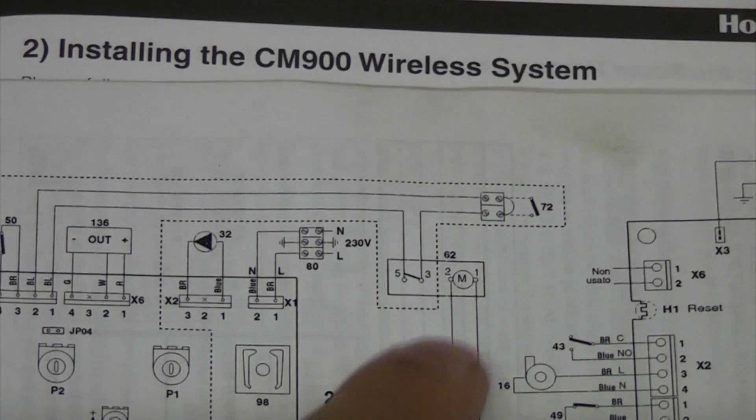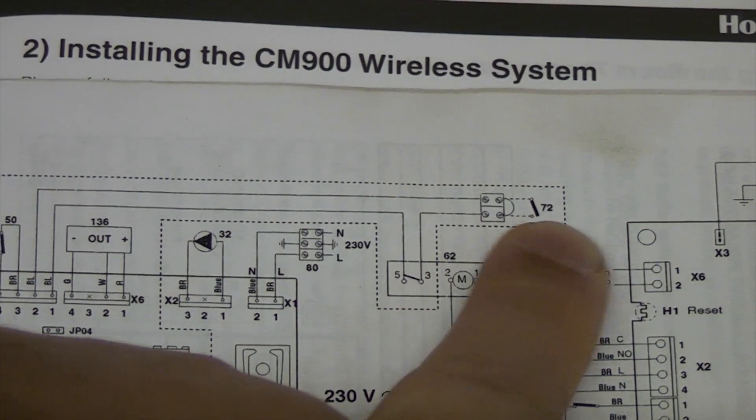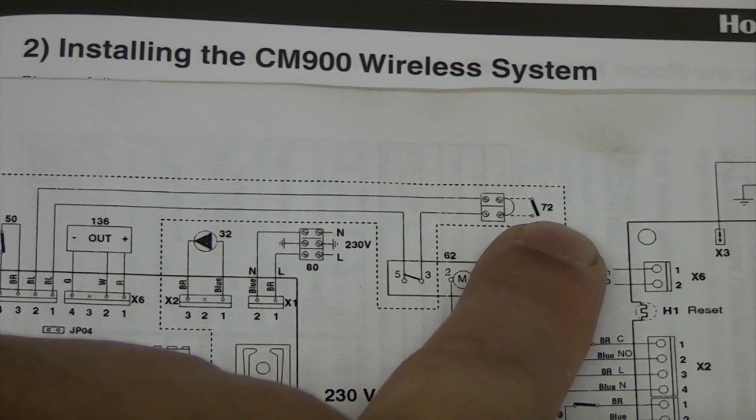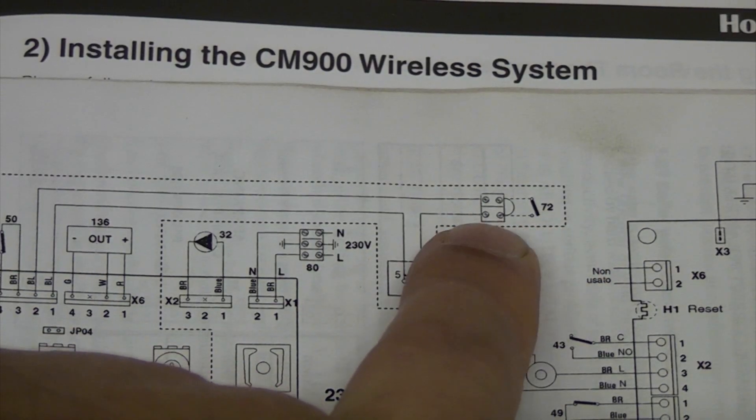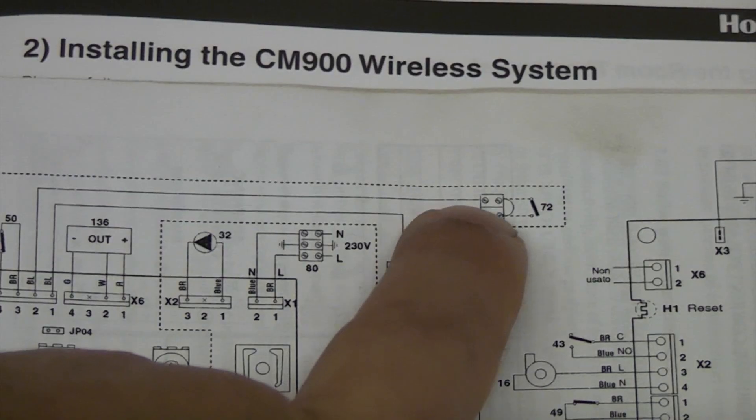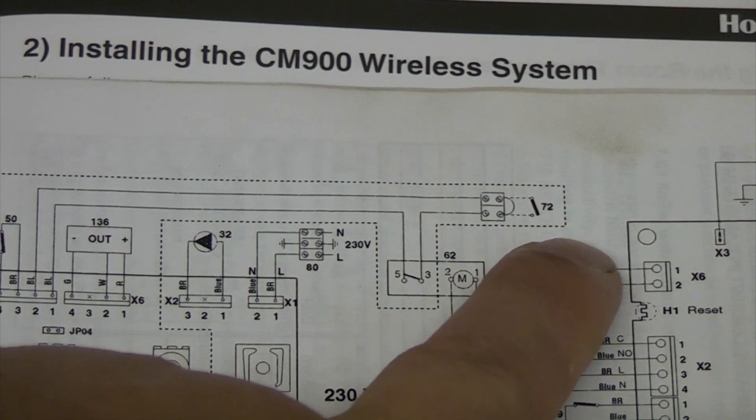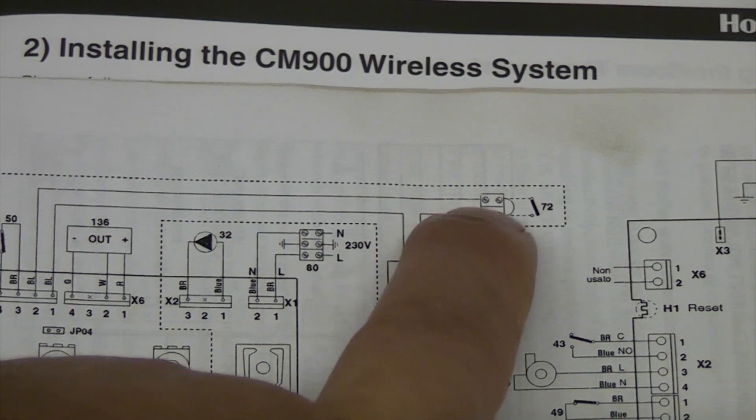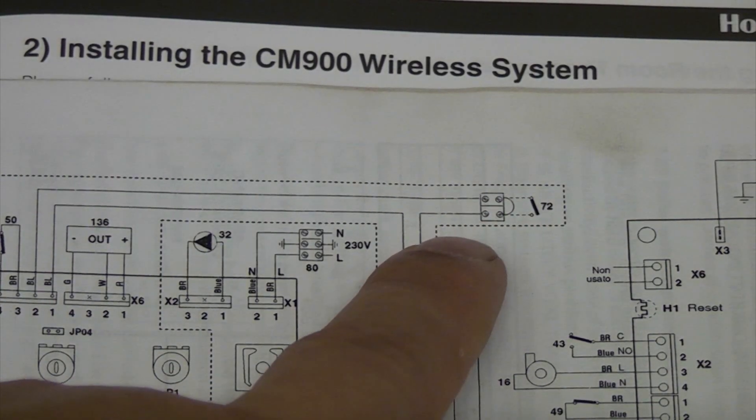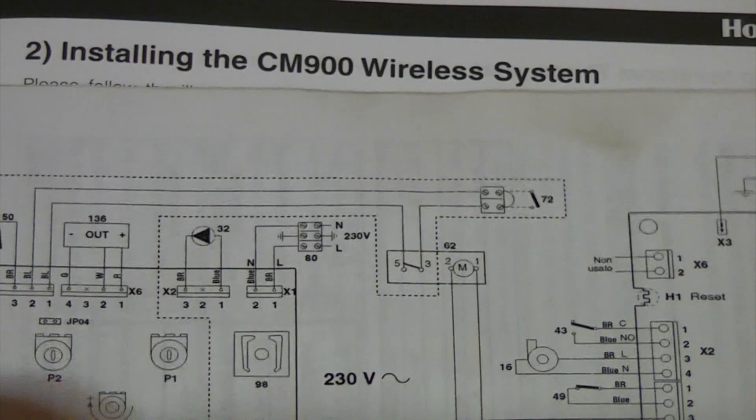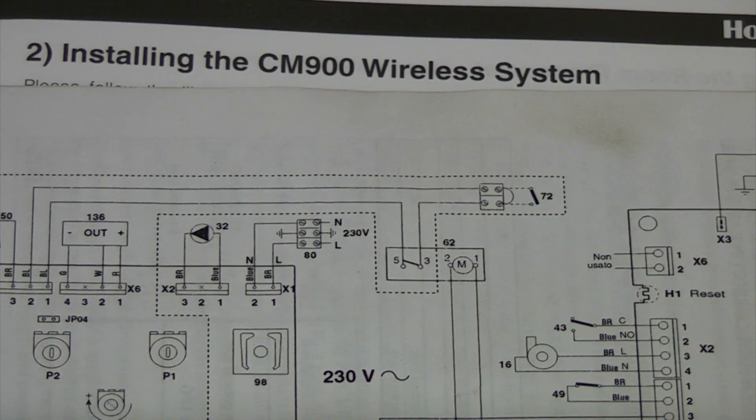So you can see there that that is terminal 72 there. So what we are looking for when we get in the boiler is a connector, and it should actually have a link in it, and what we will do is we will remove that link and then we will put one or two wires in there that are coming from the actual thermostat receiver, and that should be it. It is as simple as that.